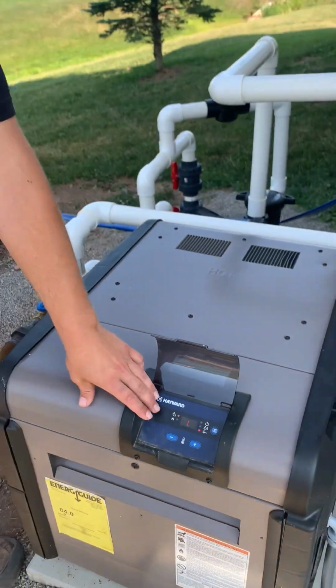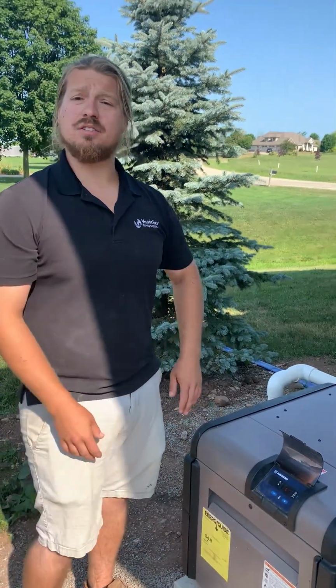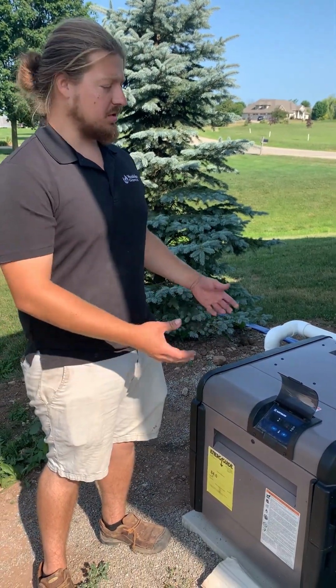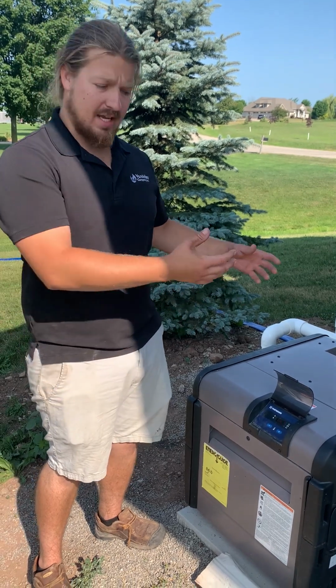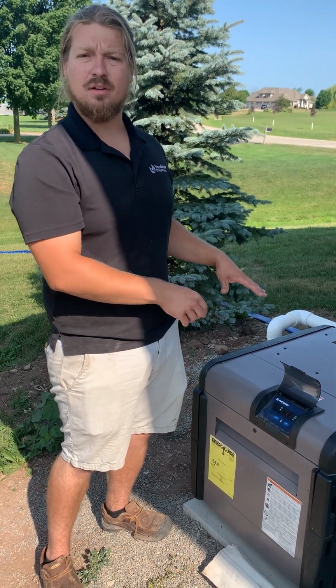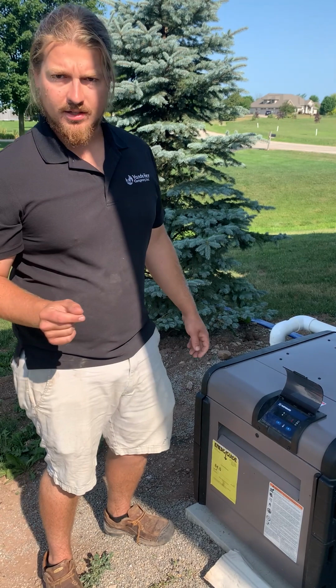So now we're seeing this LO, low, on the display. Basically what that means is it's low flow. There isn't enough water going through the heater to take all that heat out, and it risks damaging itself, so it just stops itself because it doesn't want to damage itself.